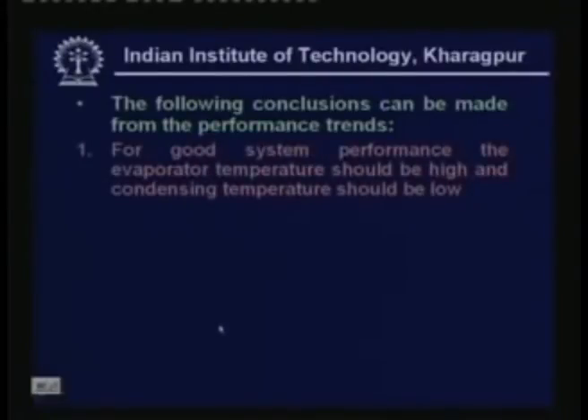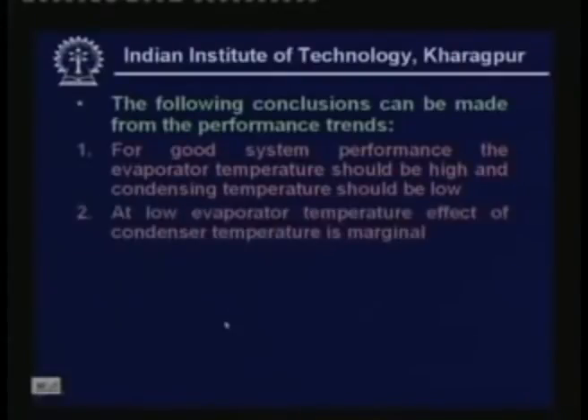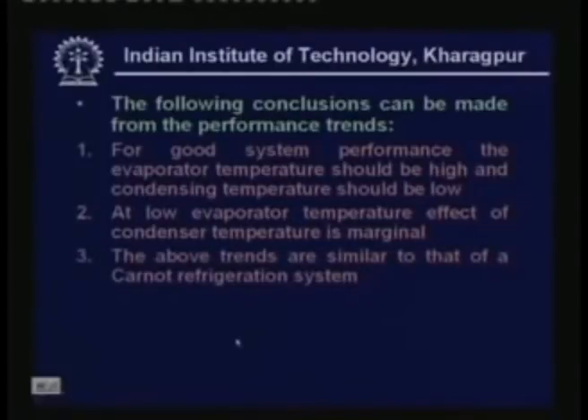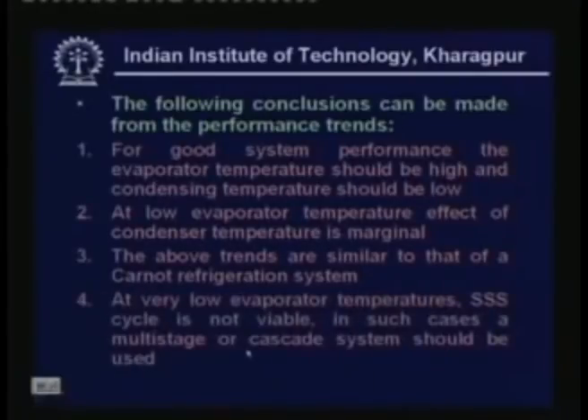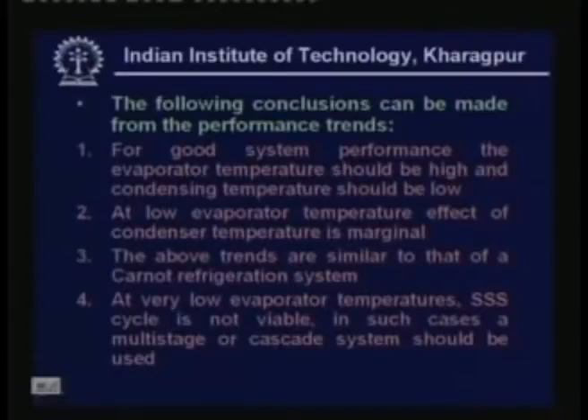At very low evaporator temperatures, the saturated single stage cycle is not viable because the COP will be small and the required compressor size will be very large. In such cases we have to use what is known as the multistage or cascade system, which we will discuss in the next class.